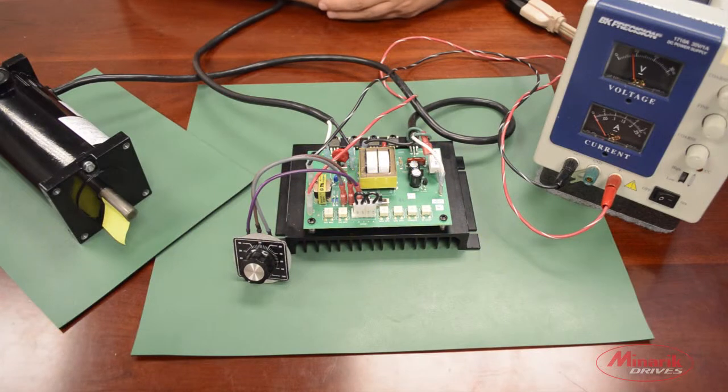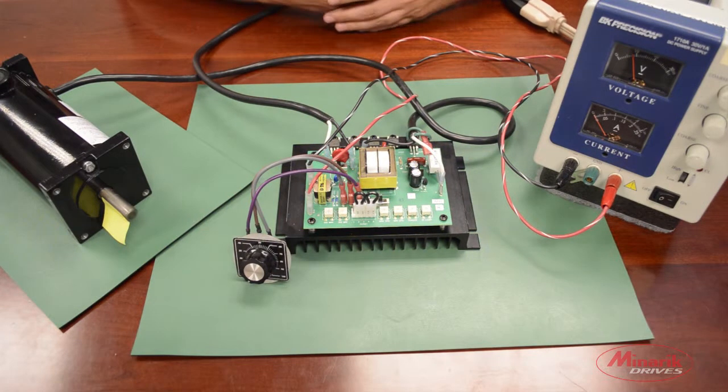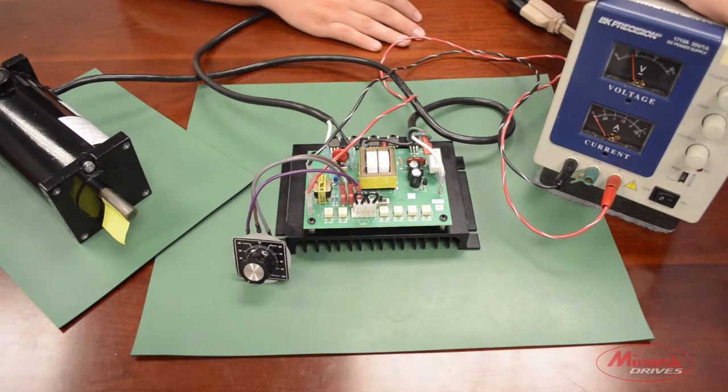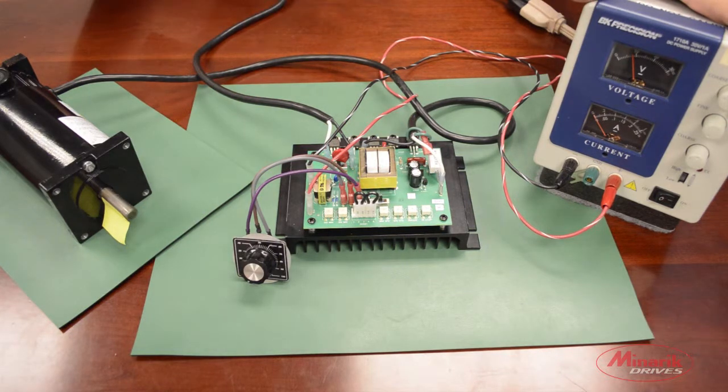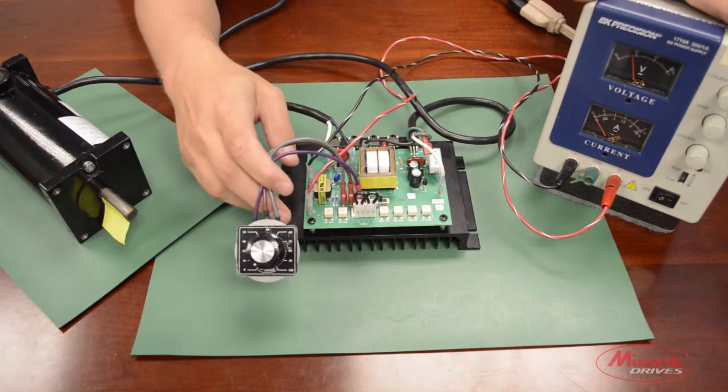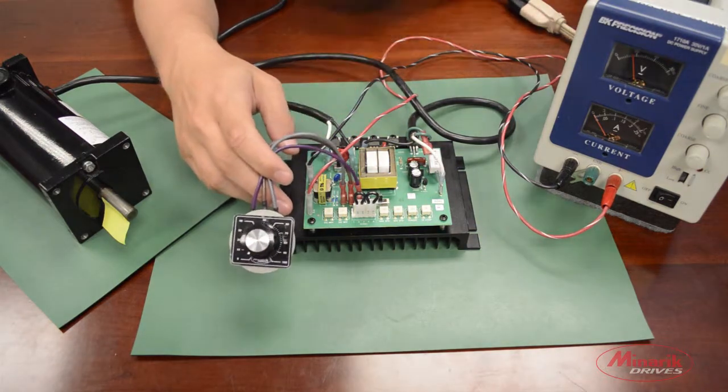Signal with ratio output mode is useful when you are using multiple drives and want to set the max speed reference for each drive. That way you can use the speed potentiometer to change the ratio on each individual drive.